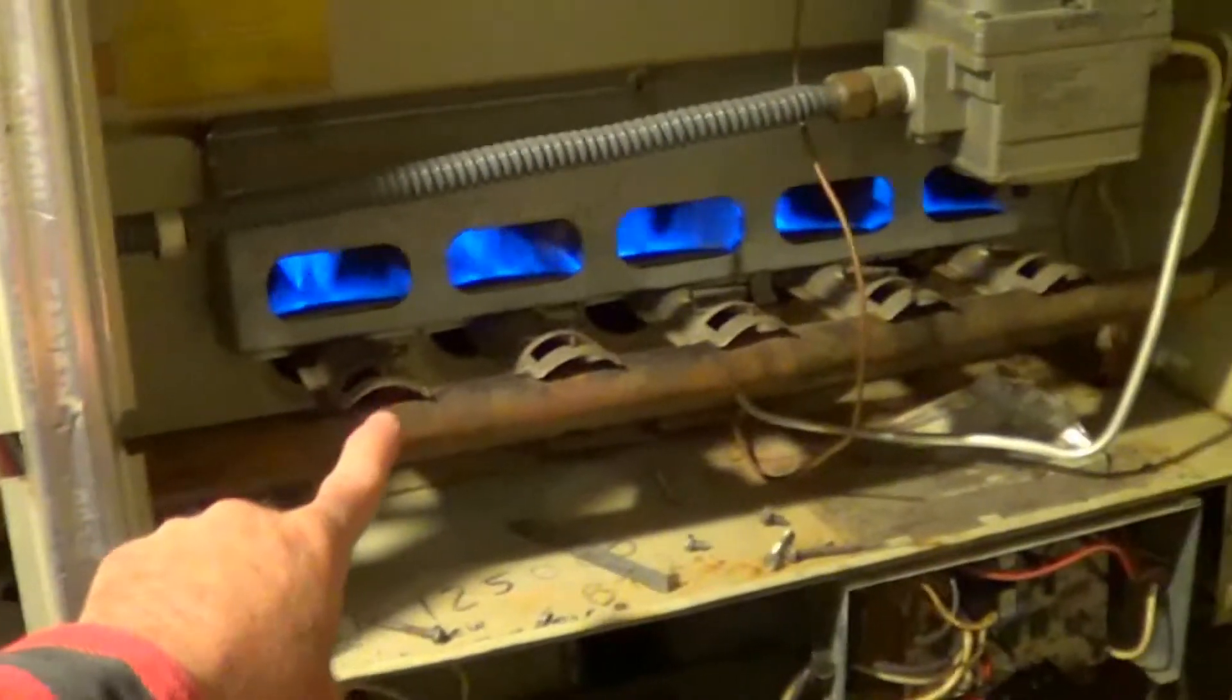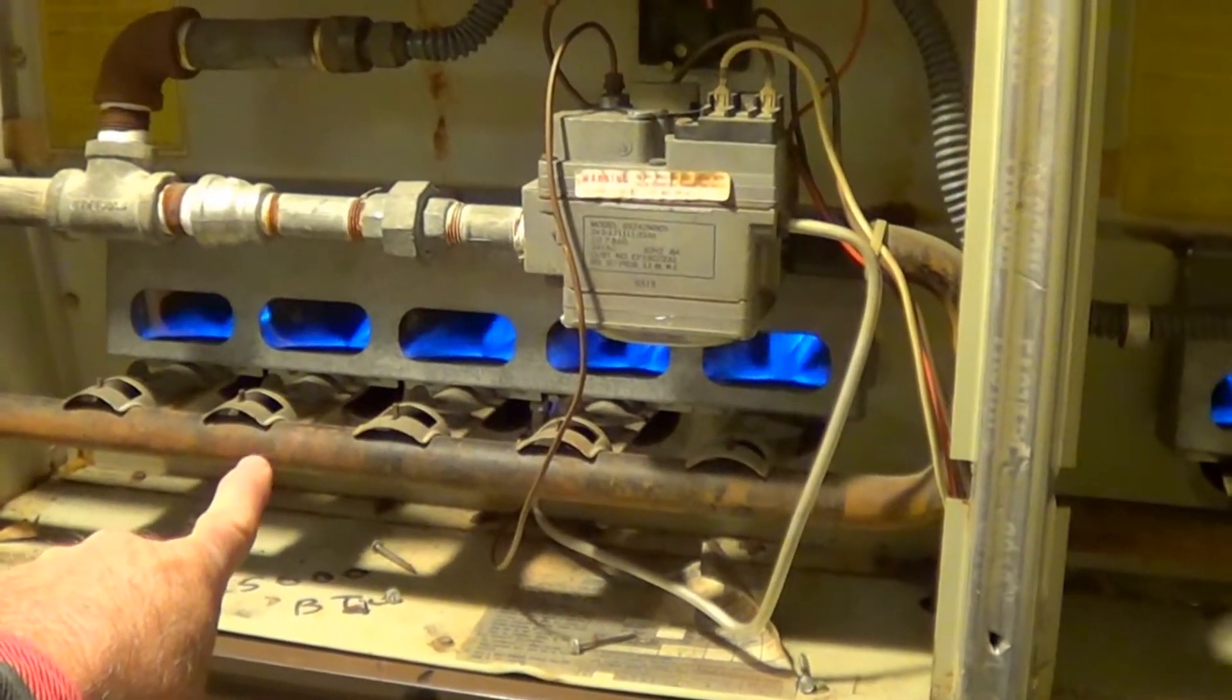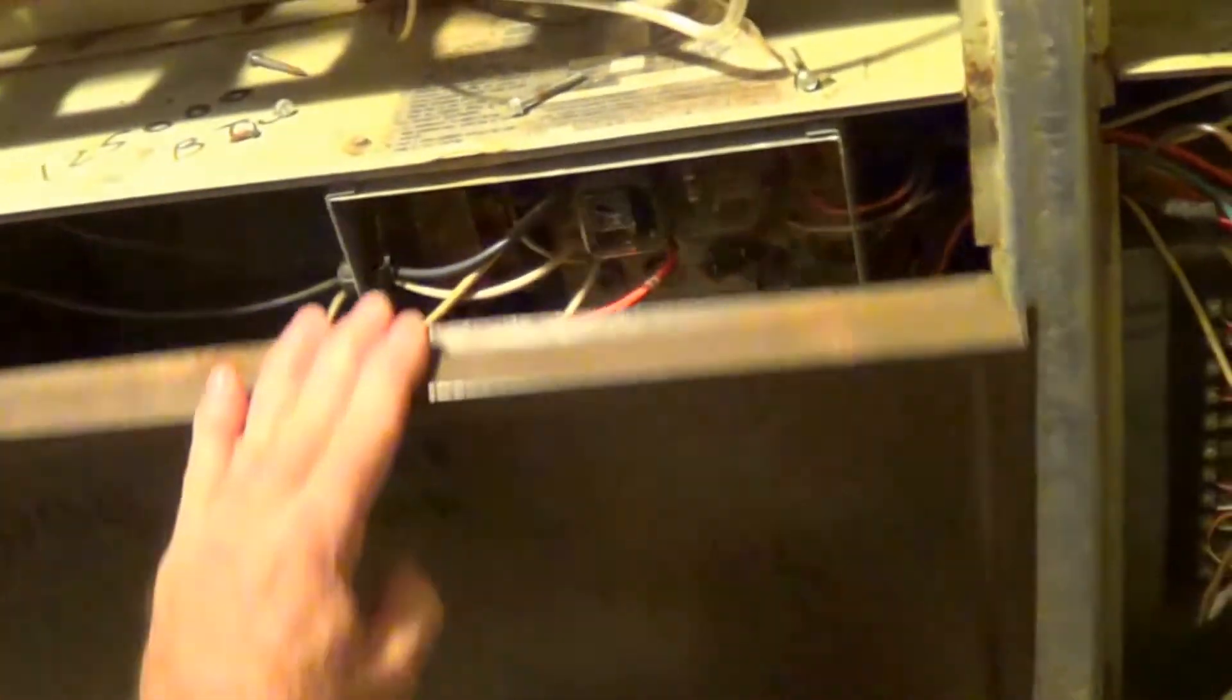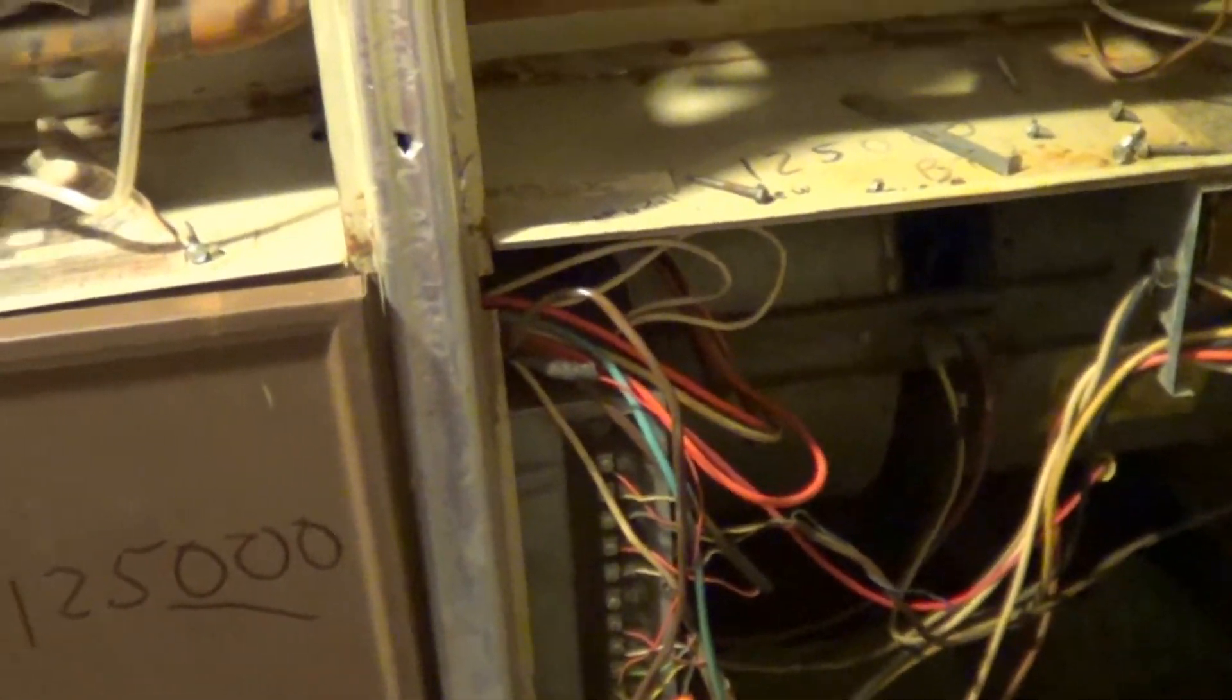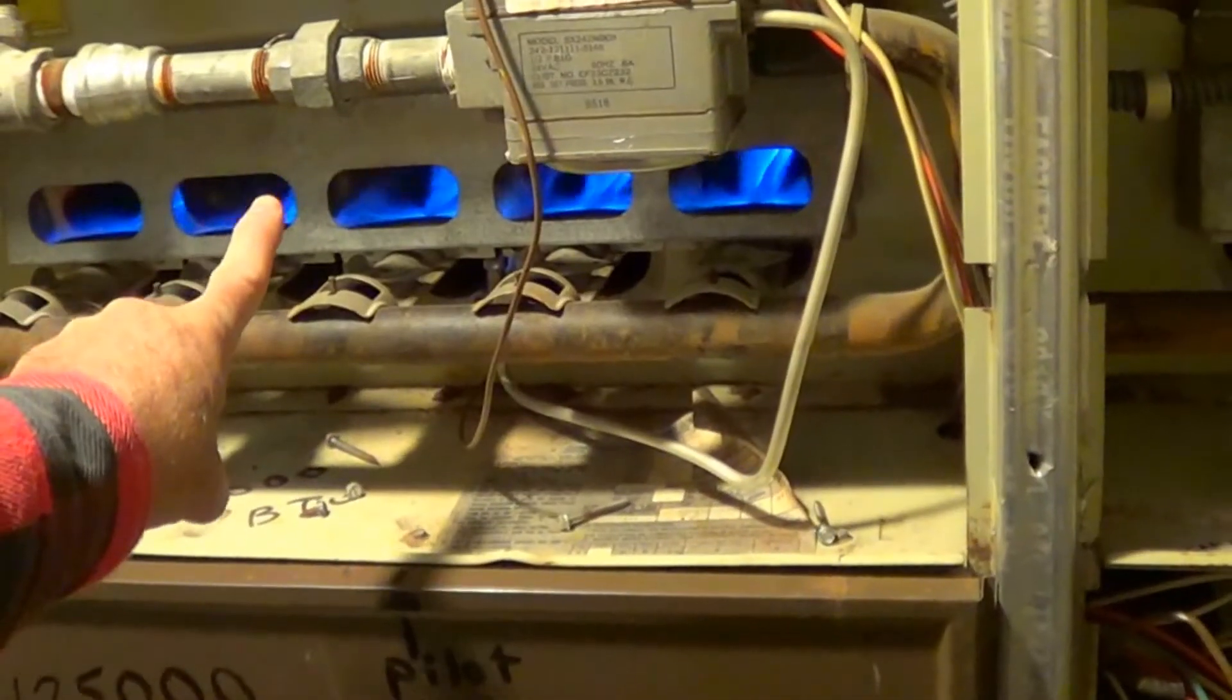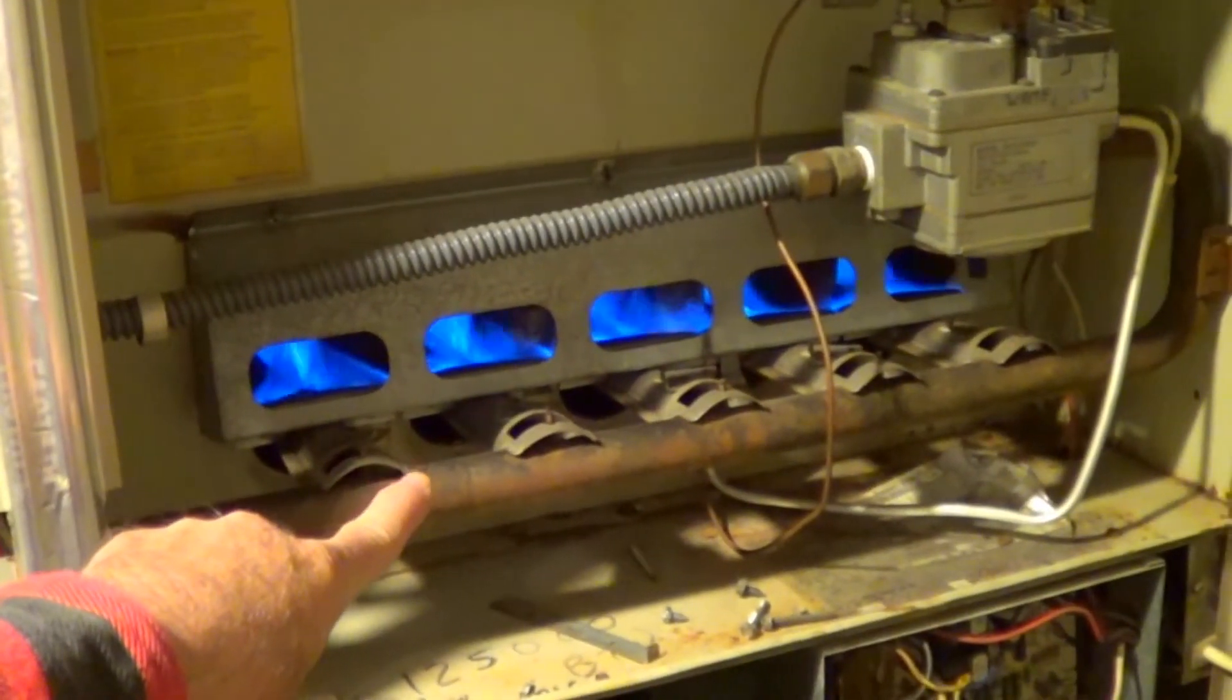Now I've got both sets of burners going. So in summary, what happens is this guy kicks on first, the right one, on a twinned unit. If there's a big delta T, it'll turn the left unit on. That's controlled by this twinning unit down here, which ties the two units together. Each one's got its own control board and they're twinned together, which is the two-stage thermostat. This will run until it's satisfied with the temperature. It'll first shut this guy off on the left, and then it'll shut the one on the right off.